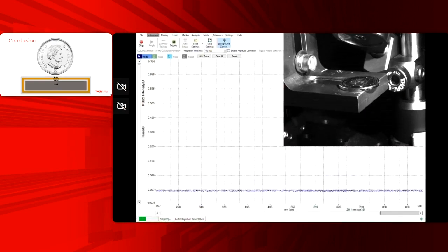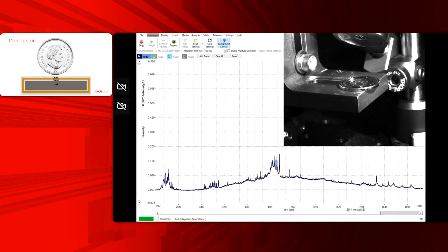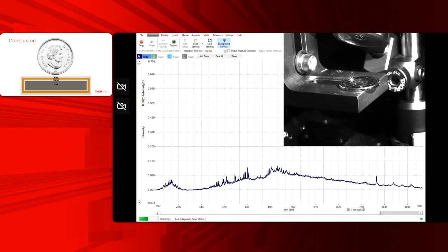All right, so you can see our system here, the coin's in the top right corner, and we're scanning across the surface, so the values will change a bit. Copper is defined by these 3 peaks in the middle here, that right there, very strong. Nickel is defined largely by these peaks down in the UV over at 200 nanometers or so. So you'll see as we go on the edge between copper and nickel, we see bits of both back and forth. Now, iron is right there.